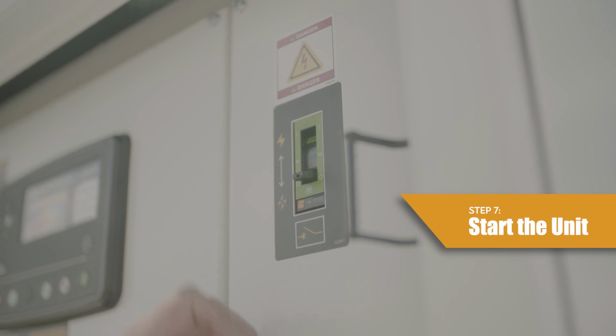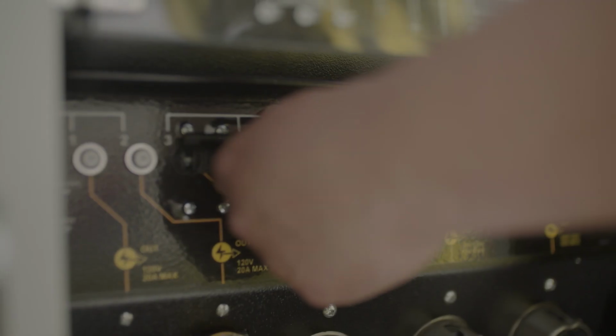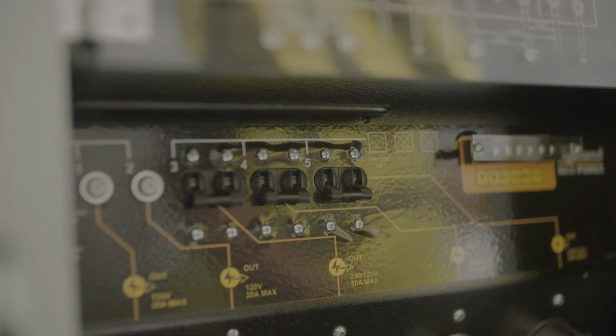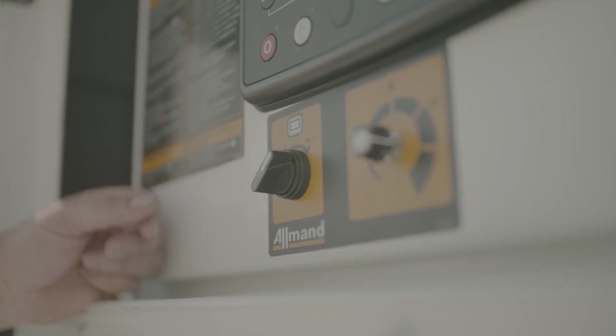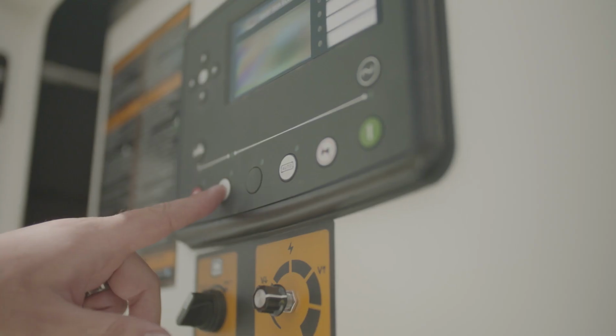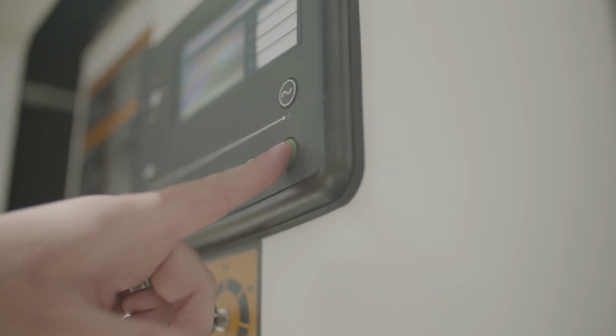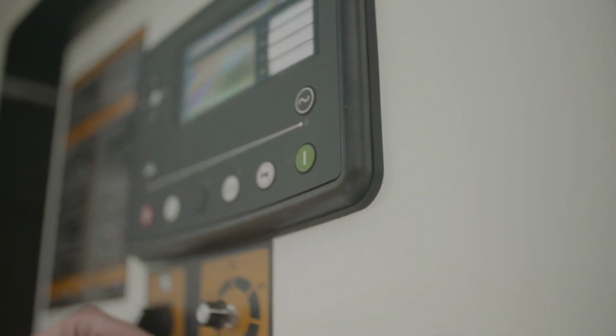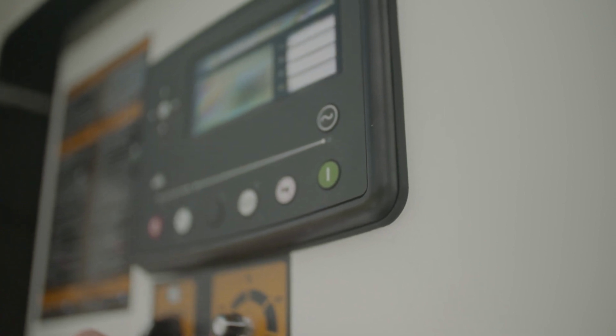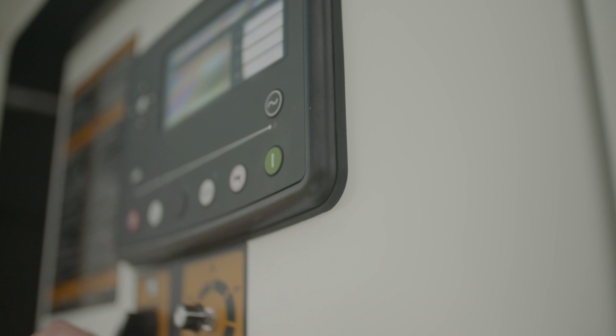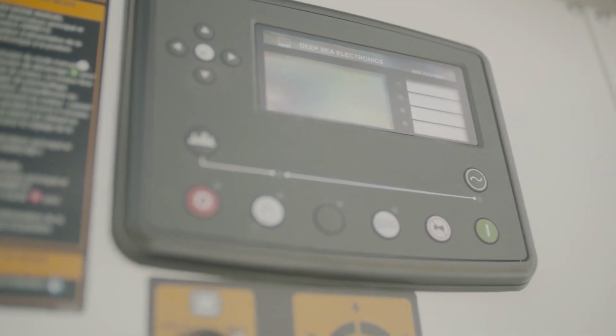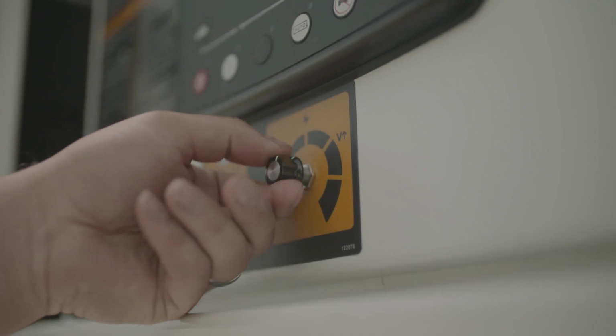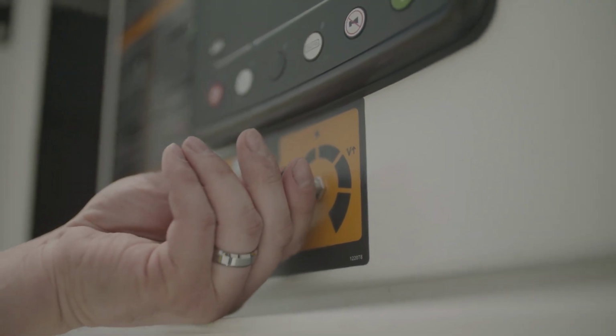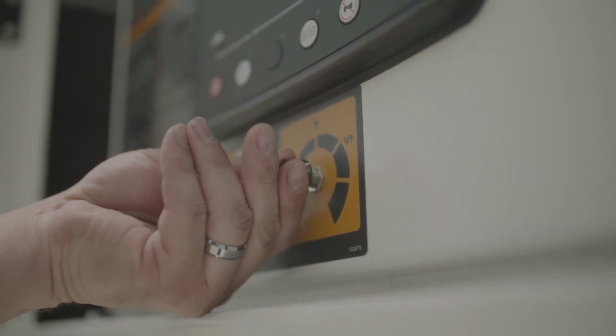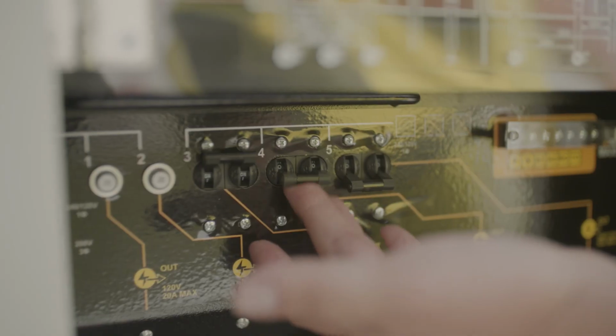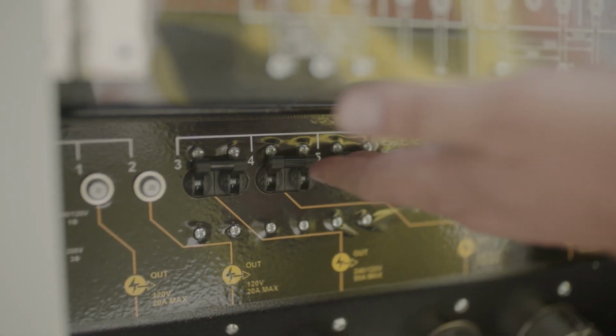Step 7. Start the unit. Set the main breaker to the off position. Set all the circuit breakers in the outlet panel to the off position. Make sure the electronic control switch is in the on position. Press the manual mode button. Press the start button to start the engine run cycle. The engine will cycle through the stages of preheat, engine start, engine warming, and engine run. Allow the engine to run for approximately 5 minutes. Note: for complete information on the Deep Sea Control Module, read the Deep Sea Control Module's operator manual. Adjust the voltage as needed by using the voltage adjustment control knob. Set all the circuit breakers, main and outlet, to the on position.